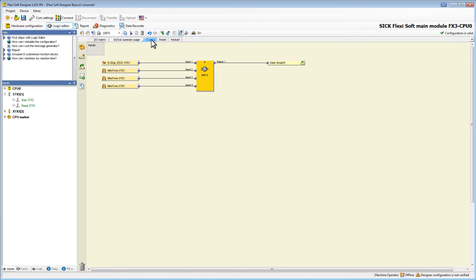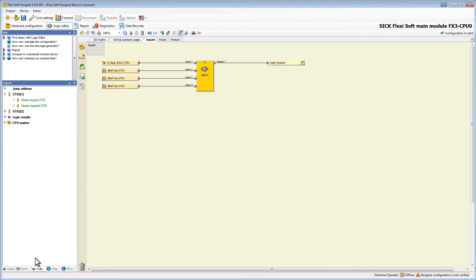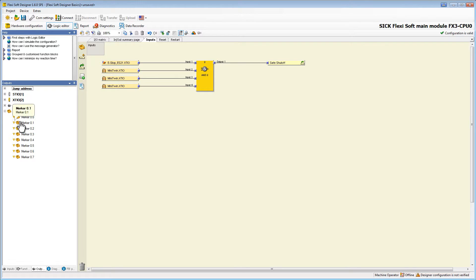The use of CPU markers works basically in the same way as the jump addresses. CPU markers are available as inputs and outputs, and contrary to jump addresses there is always a delay of one logic execution time between the output marker and the input marker. The CPU markers can be considered as variables which are readable and writable, and therefore they are available for gateway routing and other diagnostic purposes.